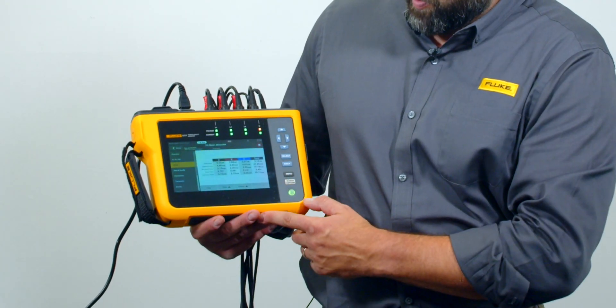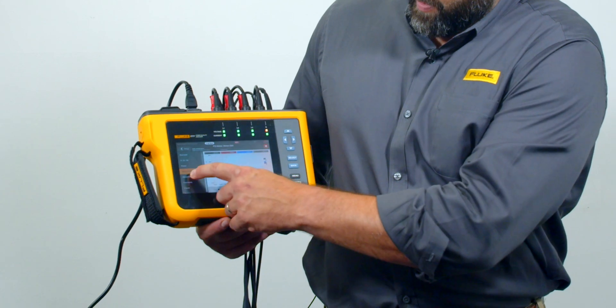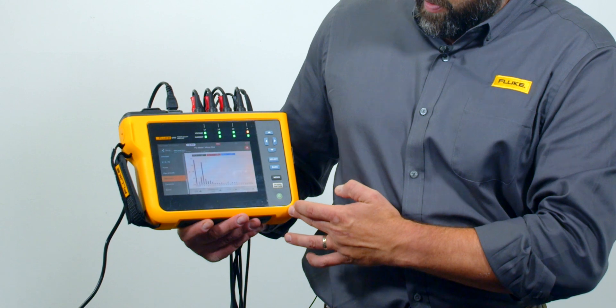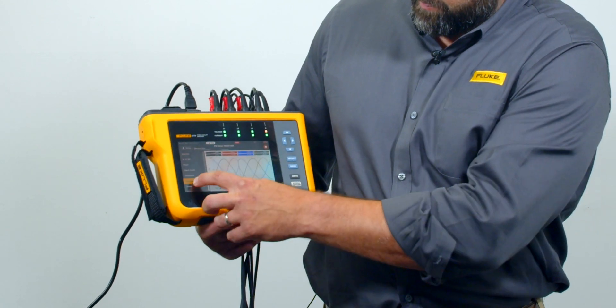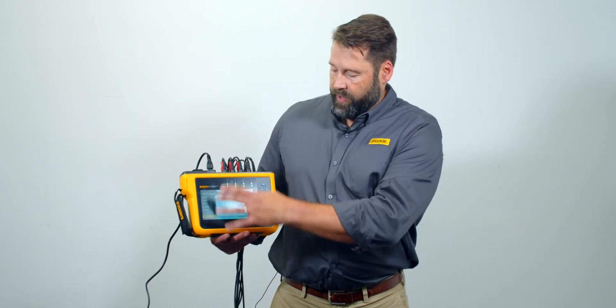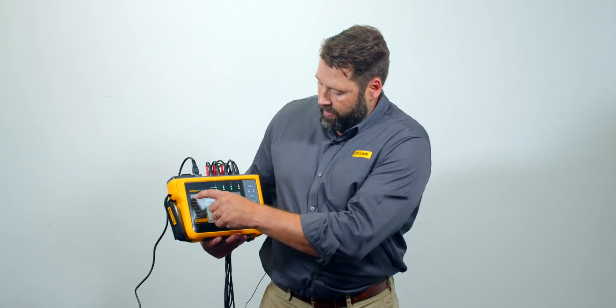I can look at dips and swells. I can look at harmonics. I can look at total harmonic distortion all the way up to the 50th harmonic. You can look at transients. This will capture events as well so if there's anything like a dip or a swell or an inrush this is going to capture it for you and it's going to date and time stamp it. It's going to put it into this table here so you can look at this.